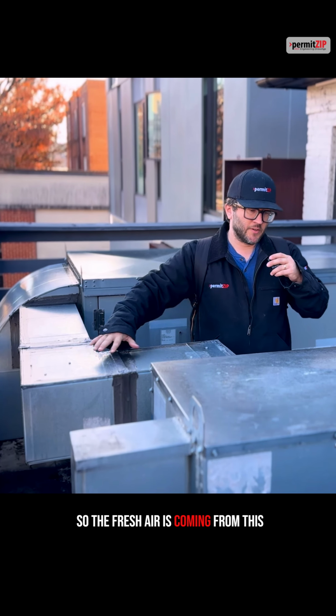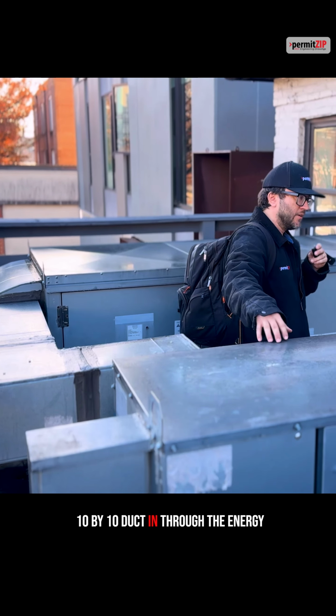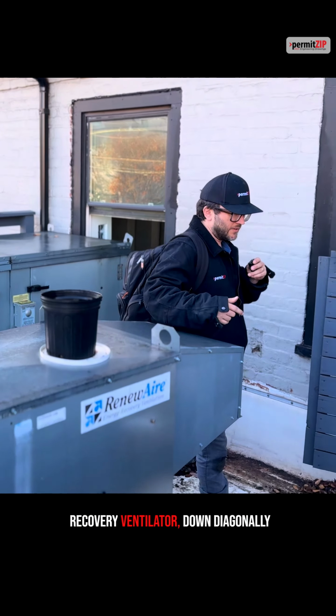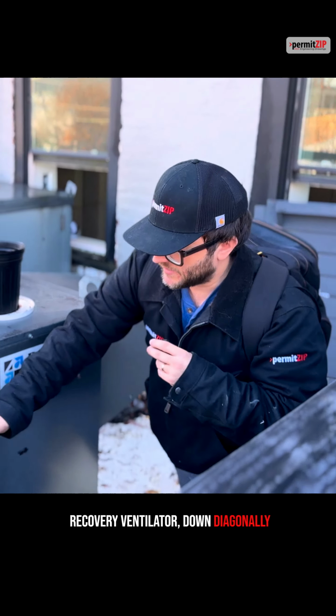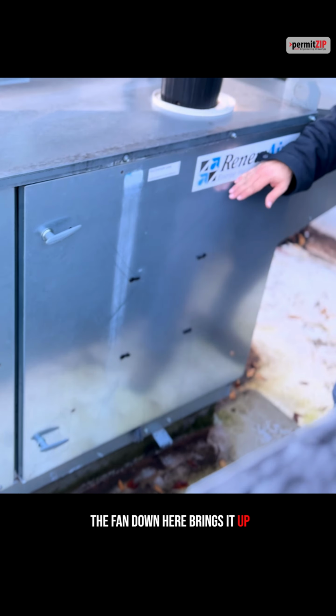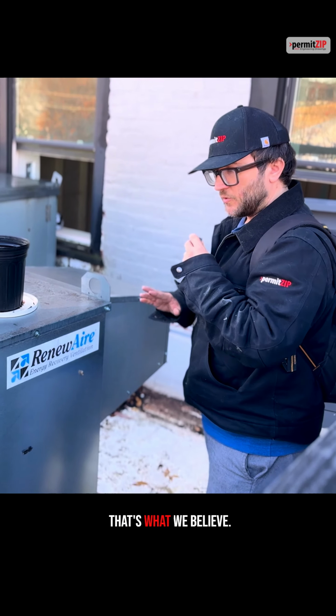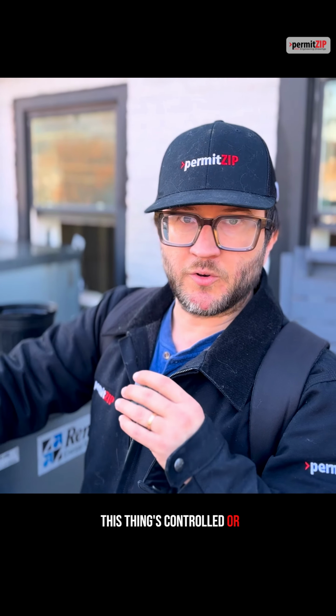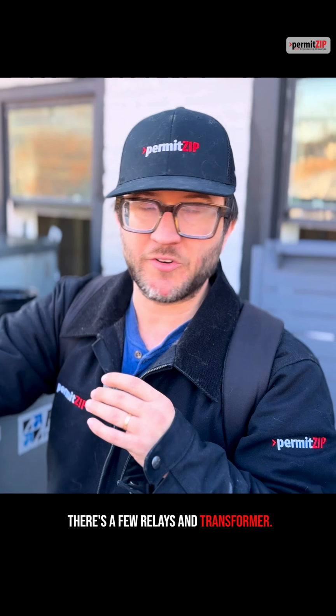So the fresh air is coming from this 10 by 10 duct in through the energy recovery ventilator, down diagonally through the core, and then at the same time the exhaust is brought in. The fan down here brings it up and out through this exhaust. That's what we believe. Currently we don't see much information on how this thing is controlled or where or how it turns on. There's a few relays and transformer.